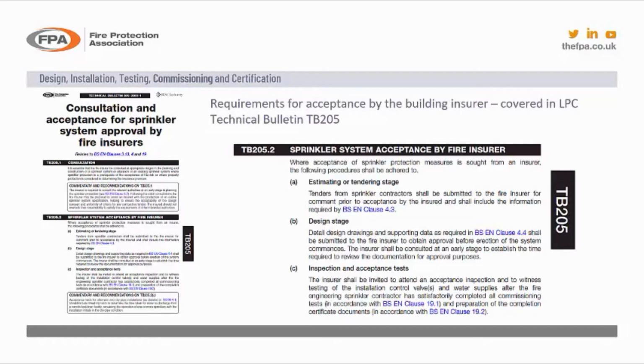Again, they also have an impact at design stage, which, going back a couple of slides, is where I was discussing that drawings must be signed off. Drawings and calculations must be signed off, and it's normally the insurers that would provide this. And finishing off on the commissioning part, obviously they need to be involved in inspection and acceptance tests. So they're there to witness, to prove that the system does what it's intended to do and that there are no issues, and in the unforeseen event that there is a fire, the system will do its intended task. So in short, when commissioning the sprinkler system, the insurer must be involved.